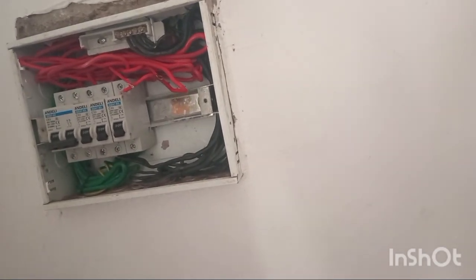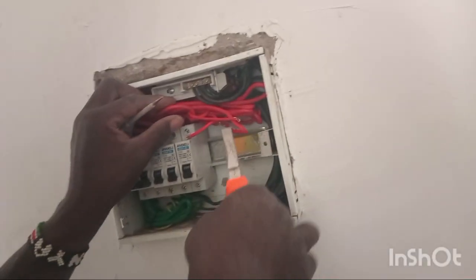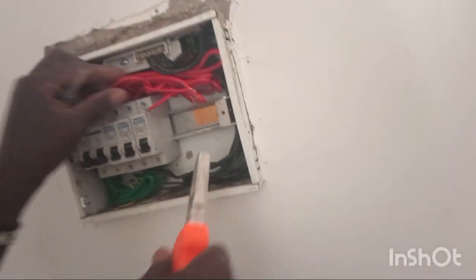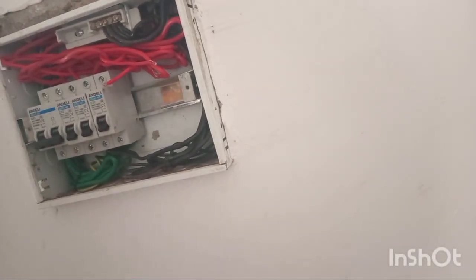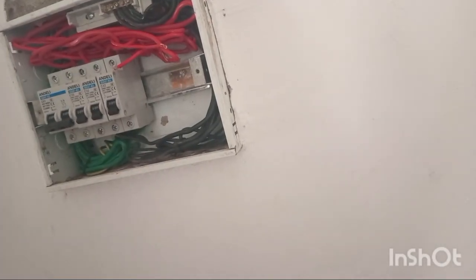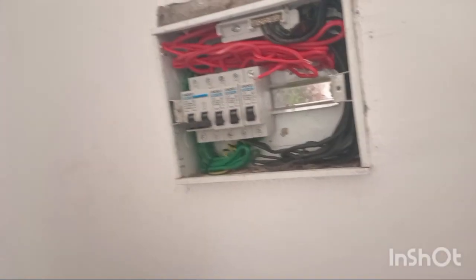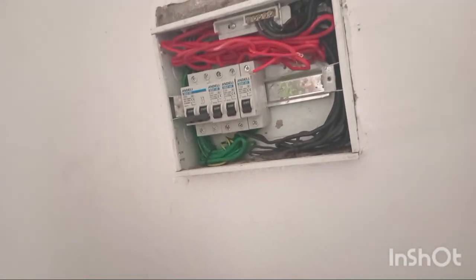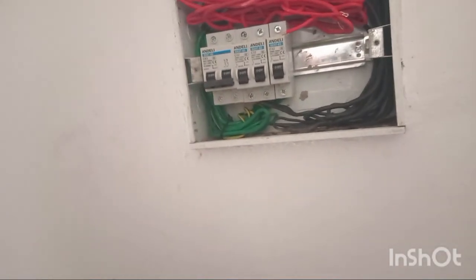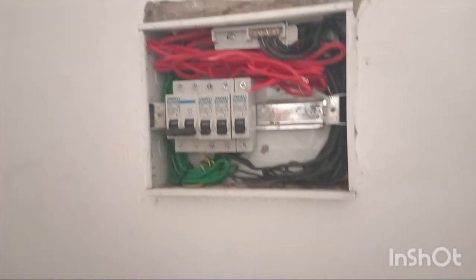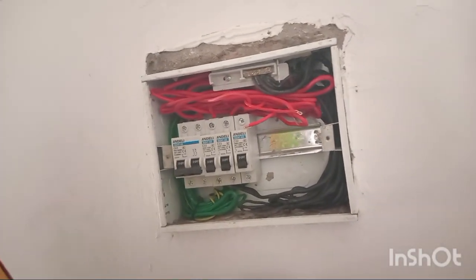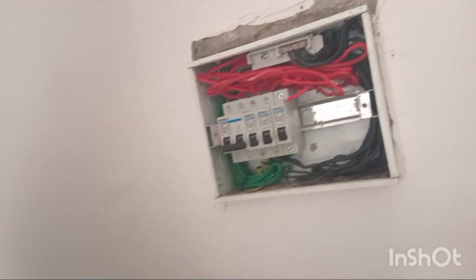The sockets now. So we're moving to the sockets. Sockets and lighting, we're going to use an MCB of 20 amperes. So for sockets we use 2.5 size of the cable. Lighting we use 1.5 millimeter squared. Cooker we use 4.0, and shower. Main supply, that is the sub main, we use 6.0.